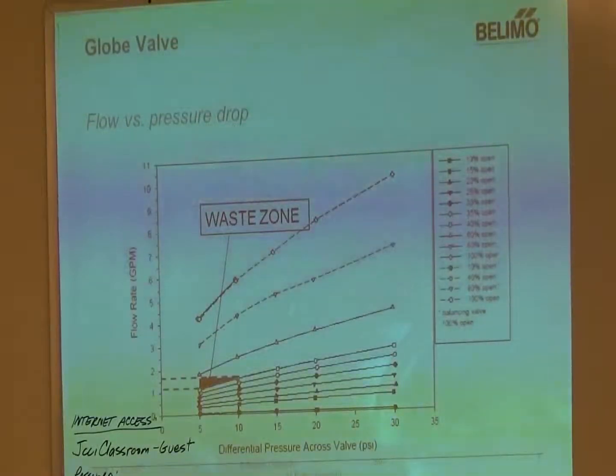Well, you may think, what's half a GPM? Well, typically, especially when we're talking about the smaller pressure independent valves, you could have a couple hundred of these on the job. So once you start talking about a couple hundred times half a GPM, you can see where you're wasting pump energy by pumping all this extra water.